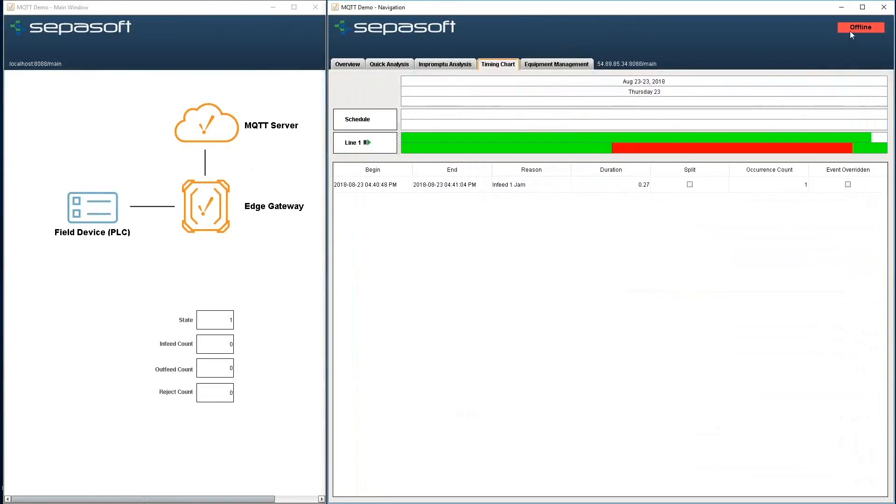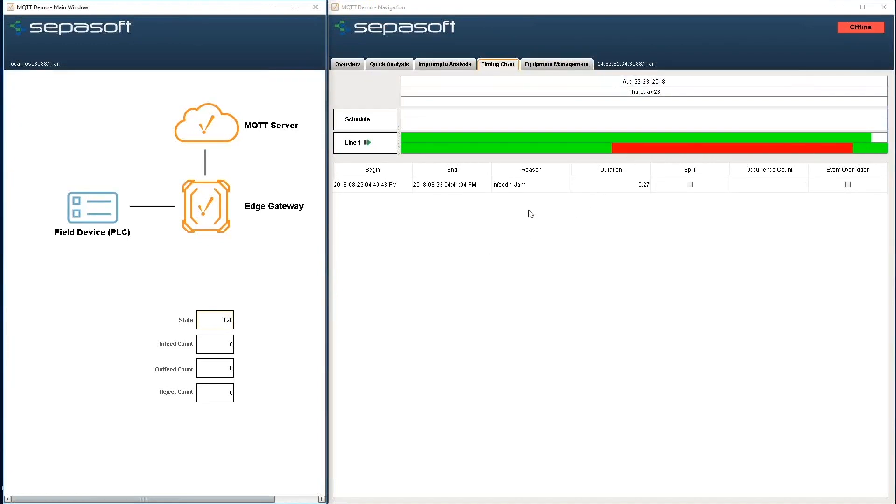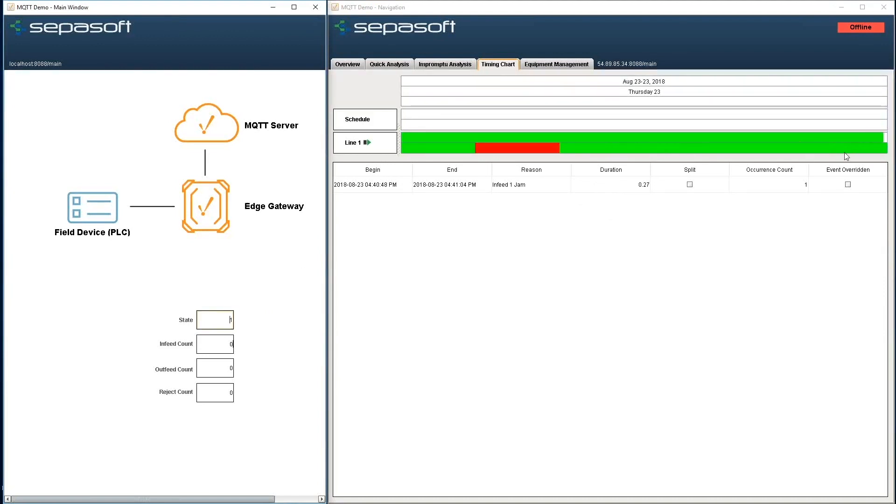We can immediately see that we're offline. Even though it's report by exception, we know it's offline right away. Now I'm going to put a different code in there, a couple different codes here, and we can see it's not updating now because we're offline. So normally this would be a gap in our data. You can see that chart didn't update, and the last data it had was it was running, so that's what it shows.